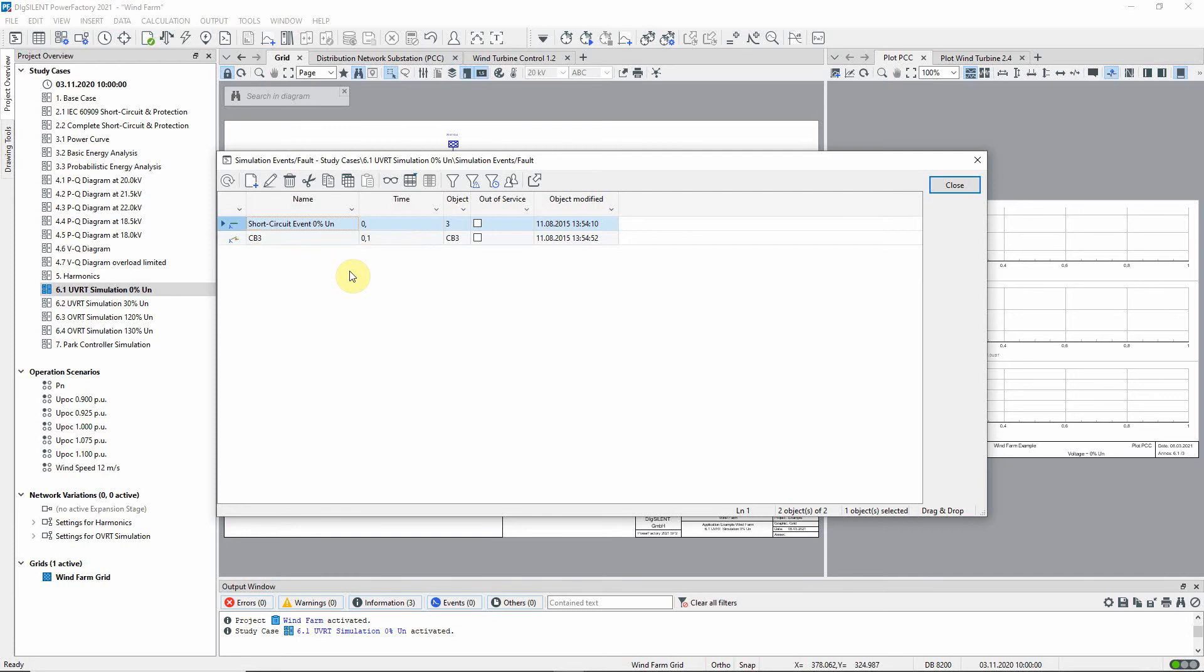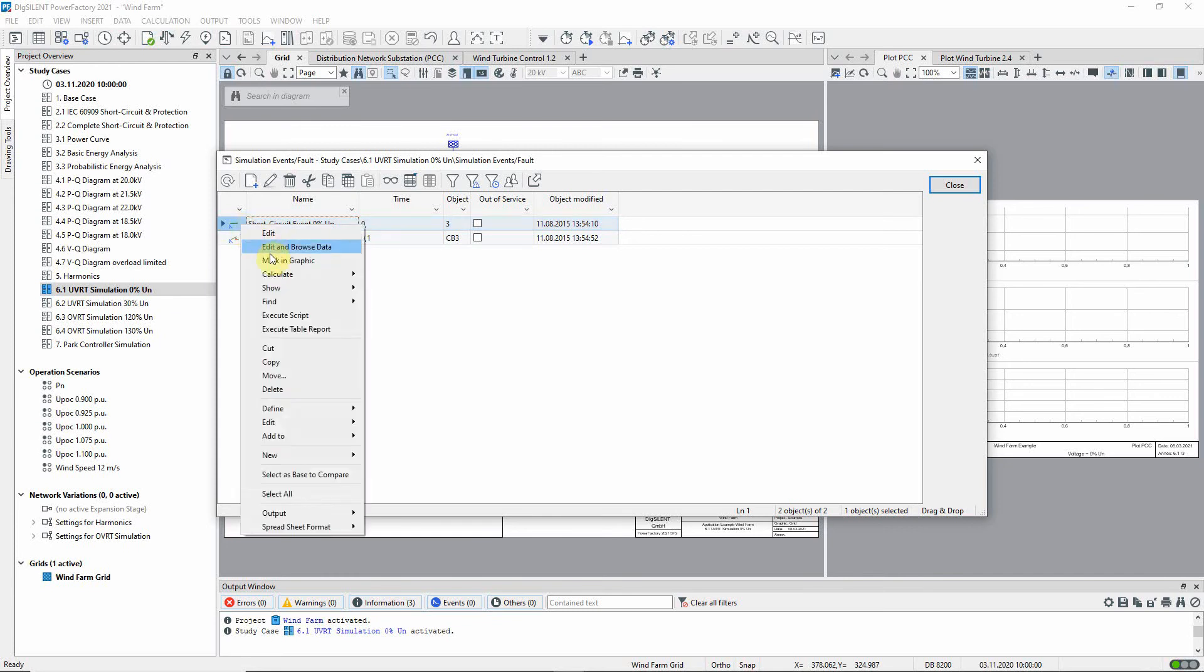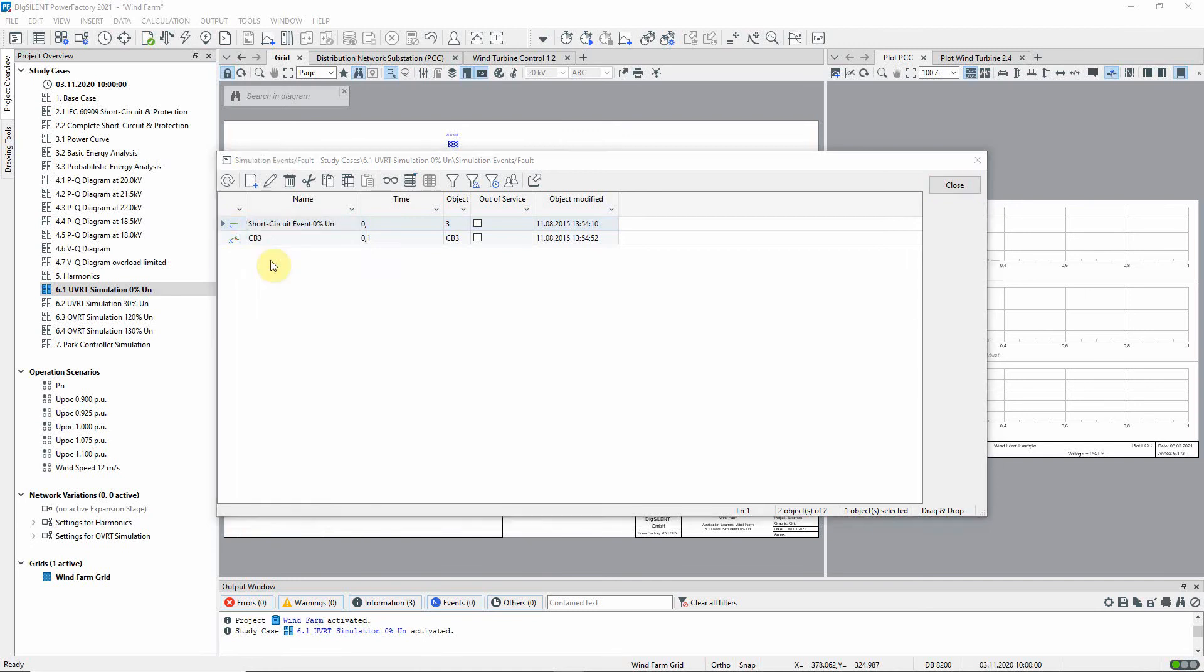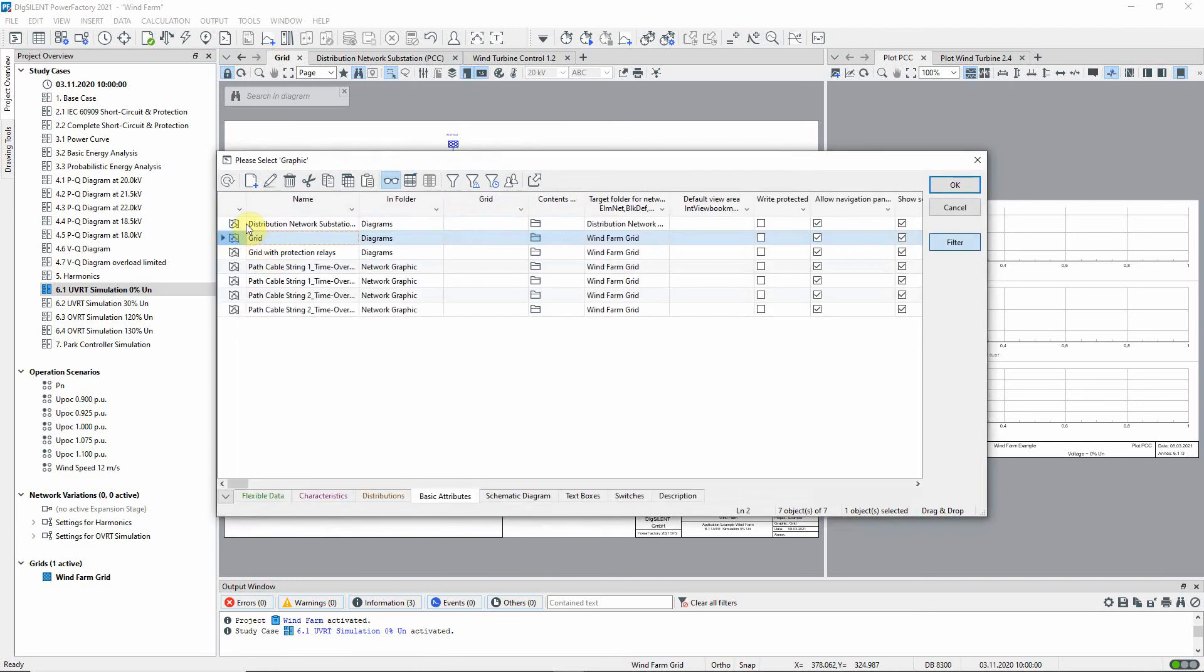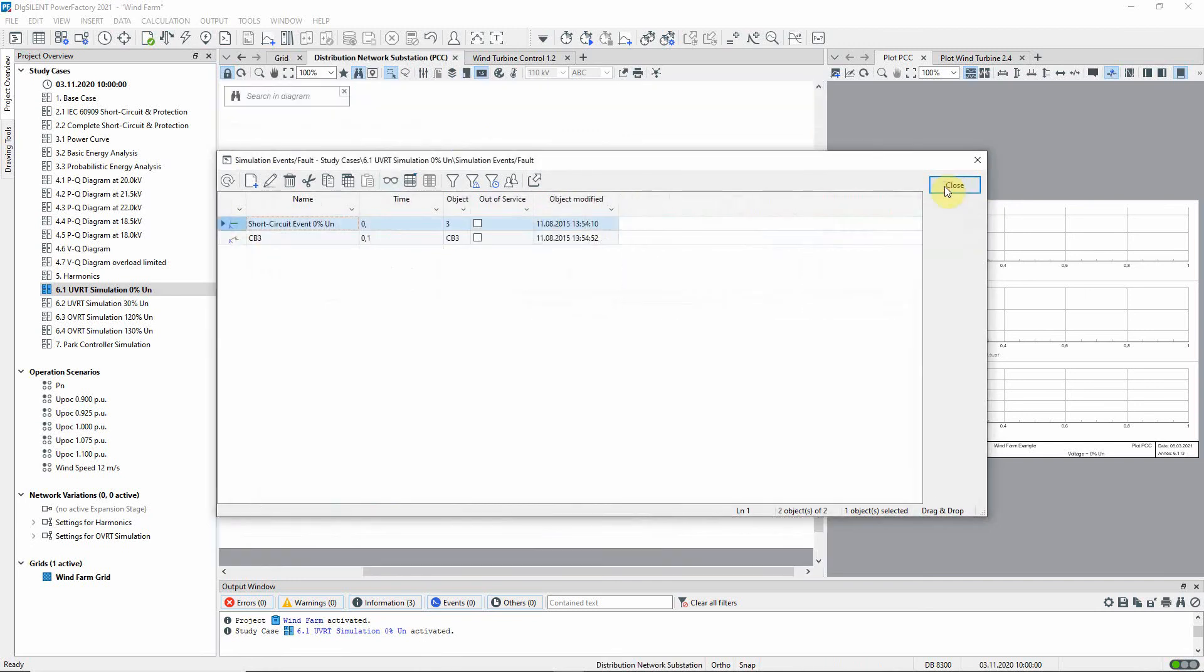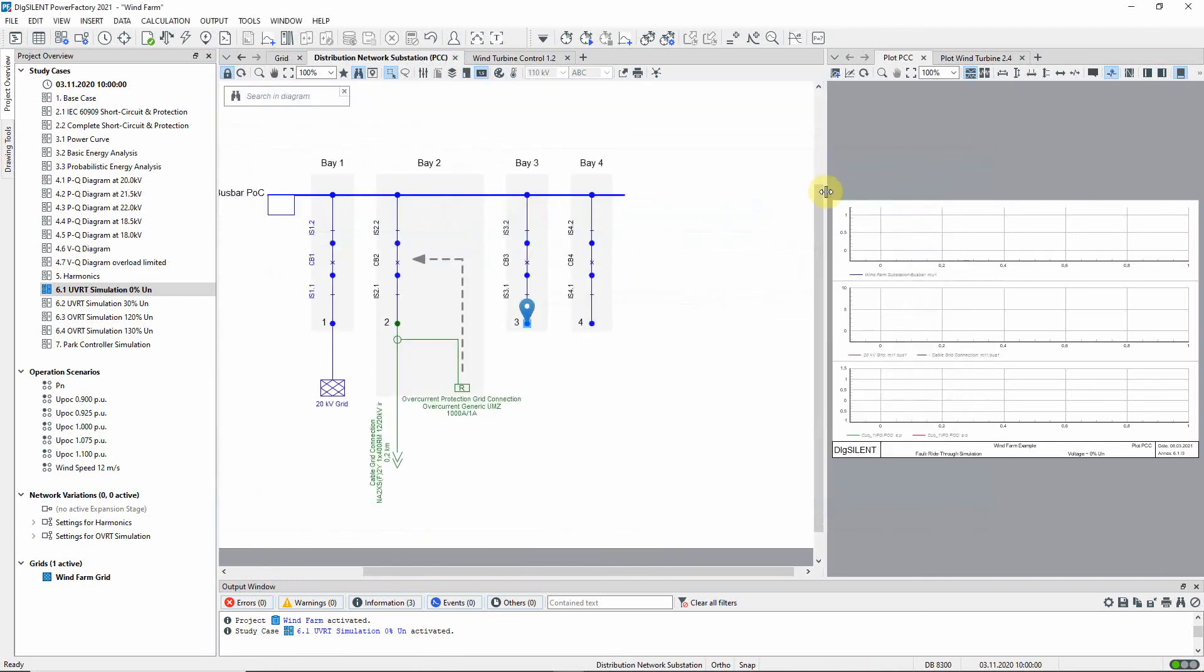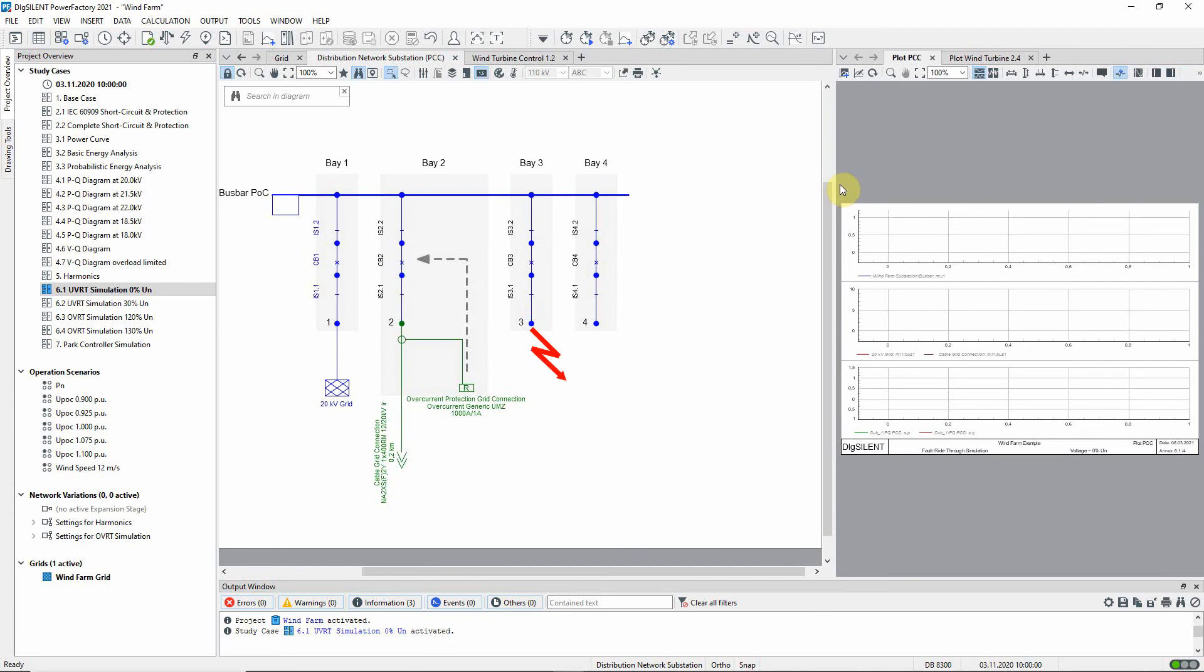The location of the fault can be shown in the graphic, by right clicking on the event and selecting mark in graphic. The short circuit is simulated at switch bay three. Due to the fact that there is no fault impedance, the voltage at the busbar will drop to zero. After 100 milliseconds the highlighted switch will open, in order to clear the fault.